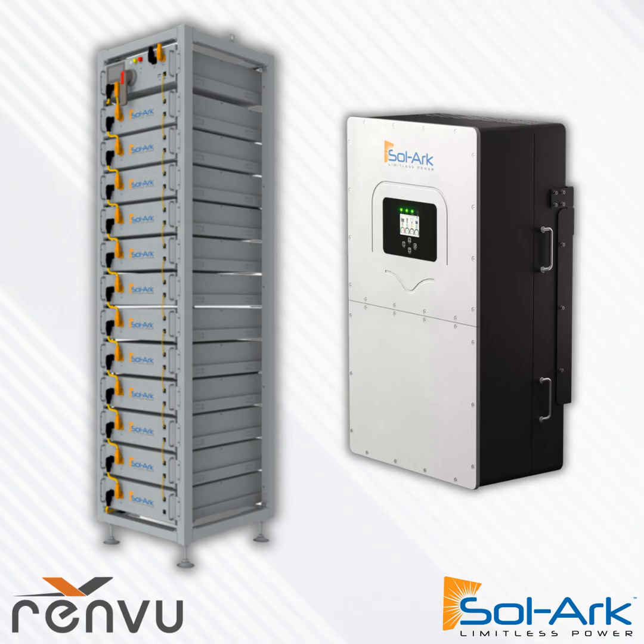Going for essential backup gets you into smaller, economically optimal projects. Even for a large facility with a 300 kilowatt load, a 120 kilowatt ESS with 240 kilowatt hours of batteries might be the right economic size. It can still provide backup power to essential loads, so the client is more accepting of a slightly longer payback than a purely economic project would require—tolerating paybacks within the 10-year warranty instead of needing something even more aggressive.